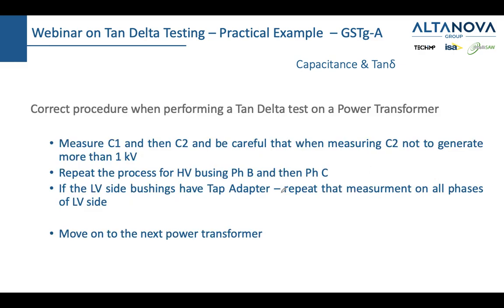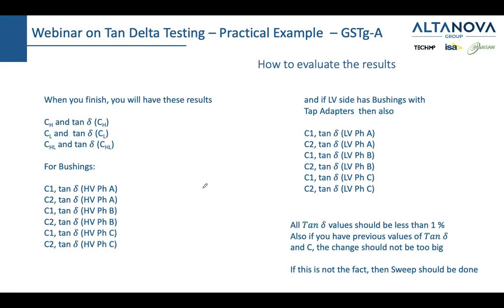So you would be measuring C1 and C2. You would be doing that for all the phases. And then you would be repeating that if you have that chance on the secondary side of the transformer. And then you would move on to the next power transformer. When you would finish, you would get these results.